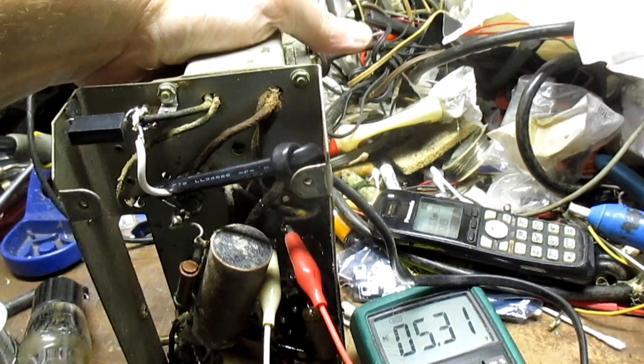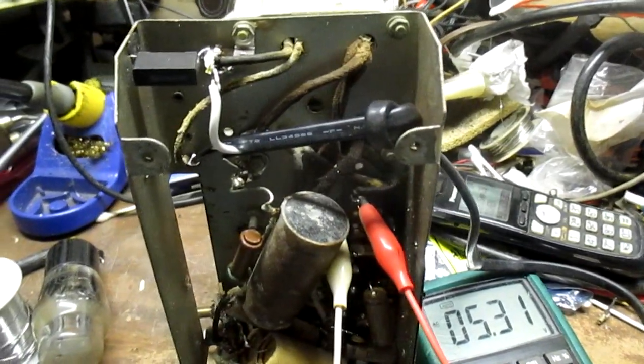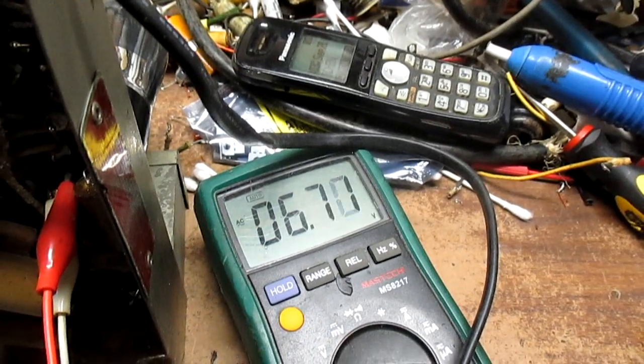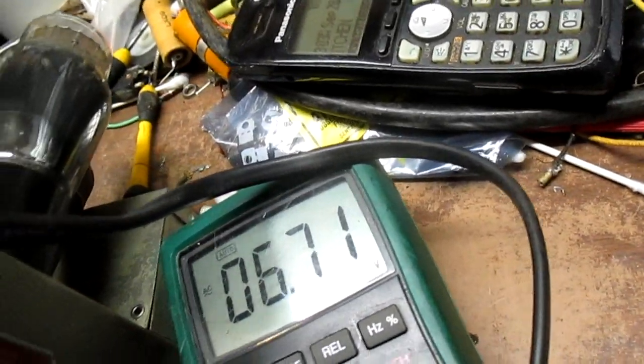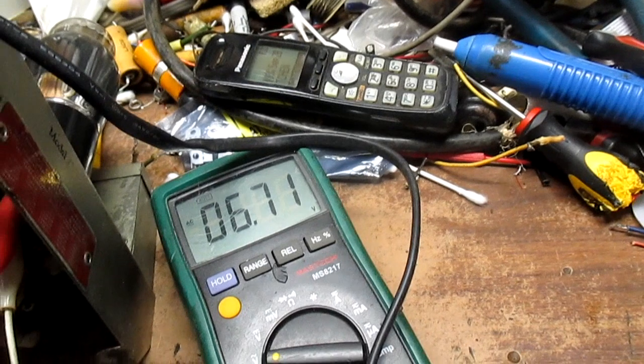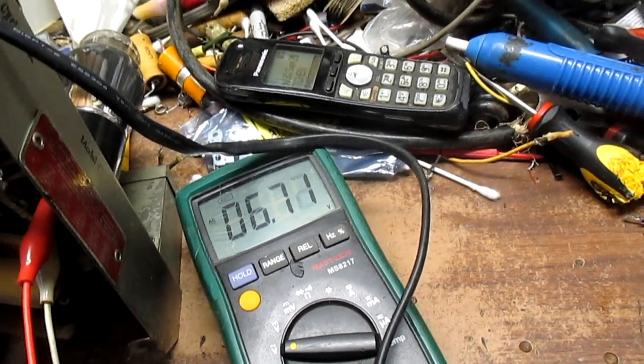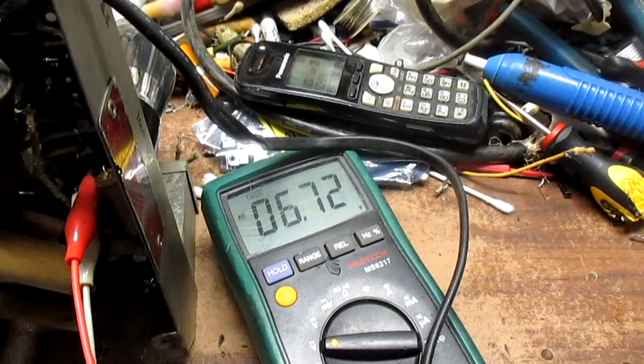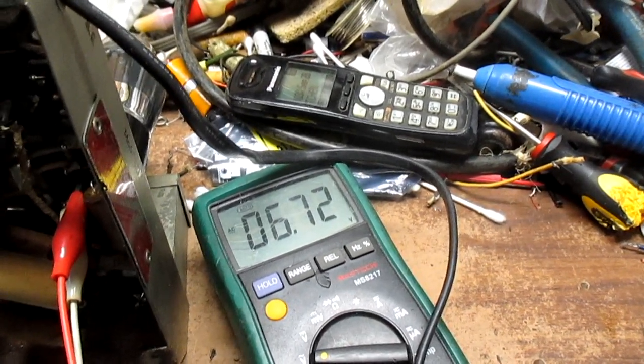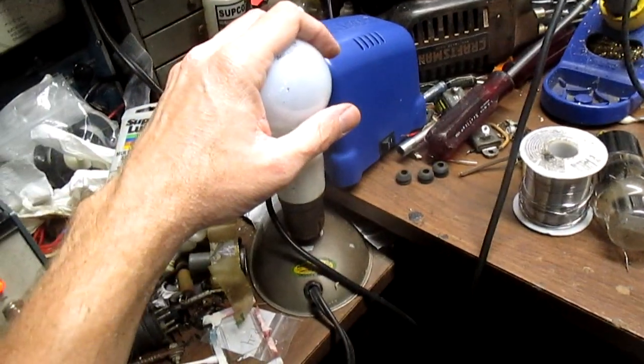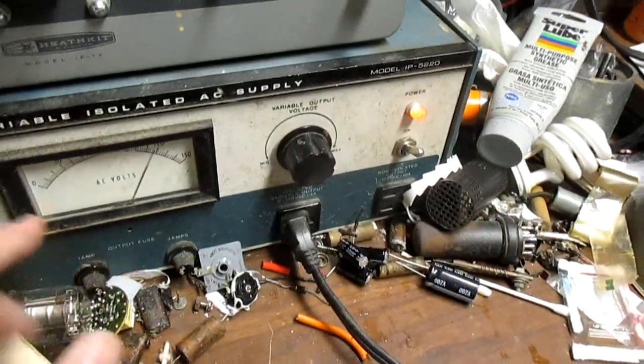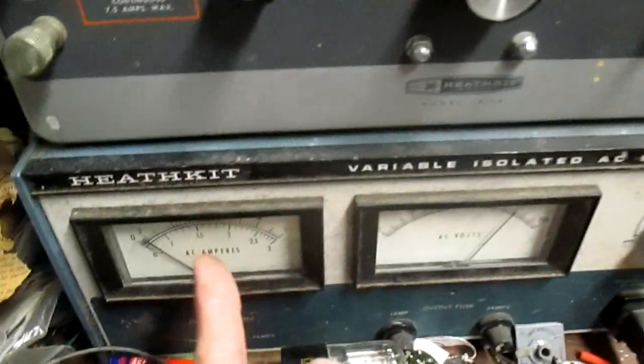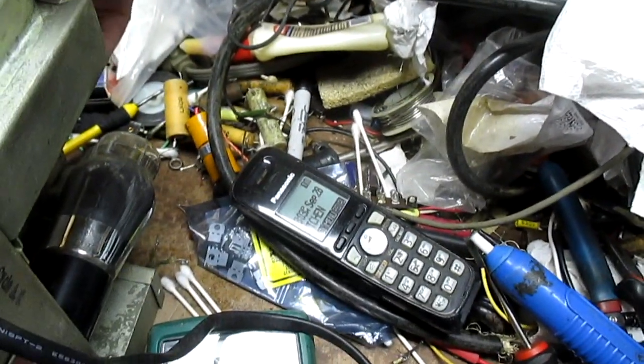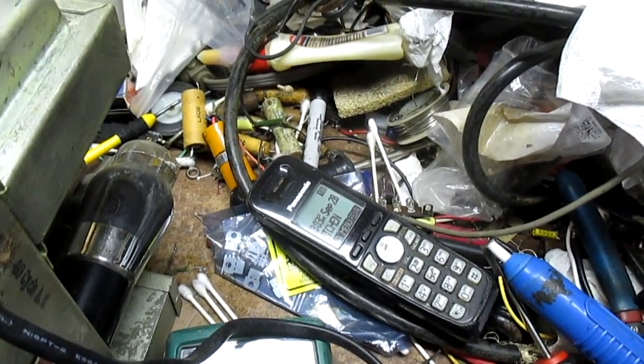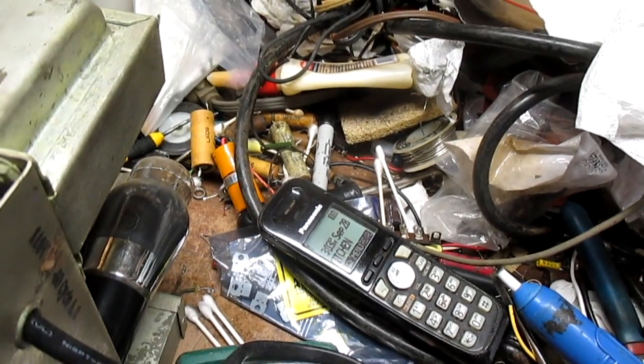We're going to have to do something to try to quieten this transformer down. The 6.3 volt winding under load, because I did not remove the tubes, is reading 6.7, so that's healthy. So electrically this transformer seems to be in good shape. We have the proper voltages coming out of it, we do not have excessive bulb illumination, and we do not have excessive current draw here. So all we really need to do to this transformer is tighten everything down and try to quieten it down, and it should be okay.